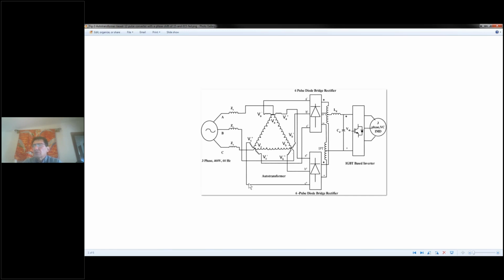and I'm not here to argue much about the better or worse of it. I just want you to be aware of it, because when you go to retrofit and you are coming in expecting a standard 18 pulse or 12 pulse transformer, you end up looking at one of these. Again, you're going to be spending a lot of money to rectify that situation as the installer or as the engineer. This type of multi-pulse system was supplied primarily by Toshiba and Allen Bradley back in the day. And again, be aware of it. Make sure you do your homework up front.